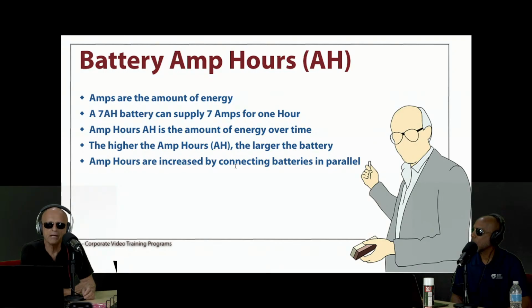Amp hour capacity is how battery energy is rated, and UPS batteries come in different amp hour ratings. The smallest one we have is a 6 amp hour rating, that's correct, 12 volt, 6 amp hour. The largest one is 140. At 7 amp hours, a 7 amp hour battery can supply 7 amps of power for 1 hour, it's that simple. So a 140 amp hour battery will give you 140 amp hours for an hour, or if you're only drawing 1 amp, then you multiply that hour by 140 and you're getting 140 hours of current or power energy, right? So amp hours is the amount of energy over time.